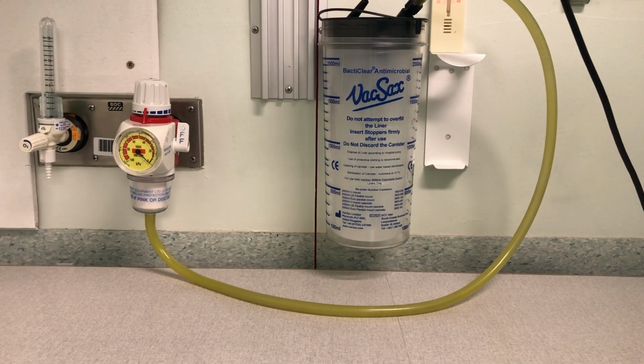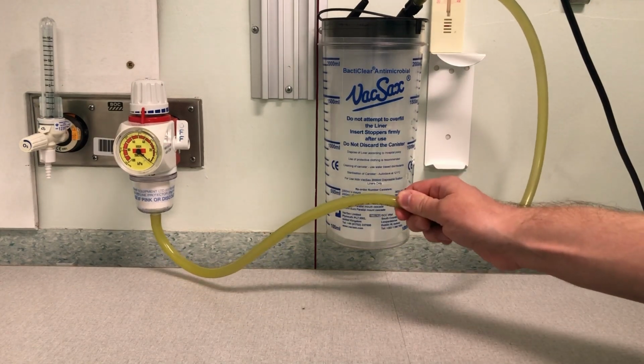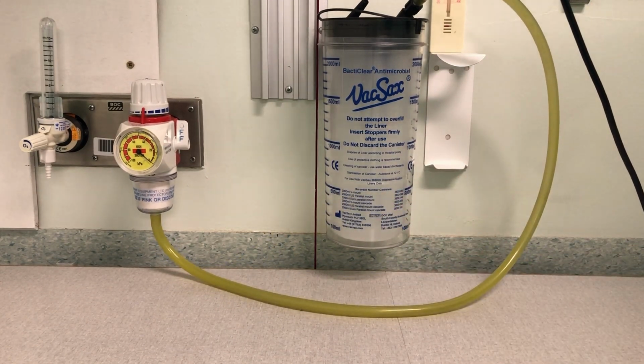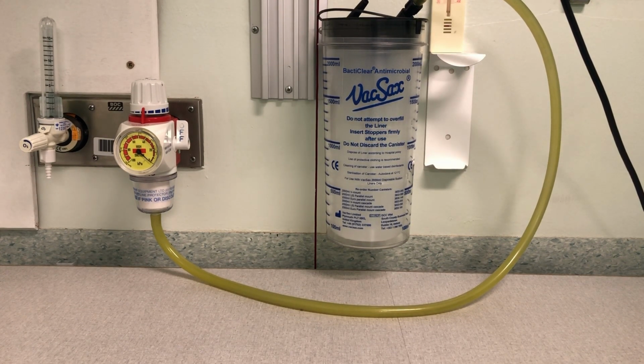So, when to change different suction tubing: yellow tubing should be changed as per local policy. It can stay in place for 2 years, however we change it yearly, and you'll see why in just a second. And the plain suction tubing that goes to the patient should be changed daily or sooner if clogged.